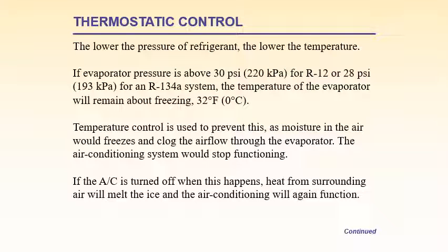As the temperature falls below 0 degrees centigrade, the air which contains moisture, this moisture will condense and form liquid particles, and these liquid particles, due to the low temperature, will freeze, and this freezing will clog the airflow through the evaporator and the air conditioning system will stop.